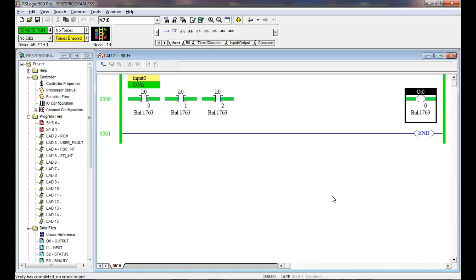So this is what I call a hybrid PLC. Most PLCs are getting away from it. You can still get the racks, but a lot of your smaller PLCs, they're going hybrid, so you can expand them if you need to, right? In the old days, like the MicroLogix 1000s that we have over there, those are fixed PLCs, which means what? You get what you pay for. You don't get any more, you don't get any less. So you can't add more outputs to that thing. You can't add more inputs to that thing. You can't add analog to it. You can't add anything to it. You can't change its communication features.